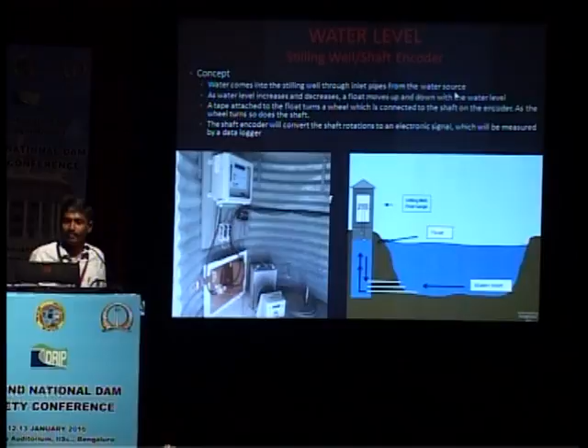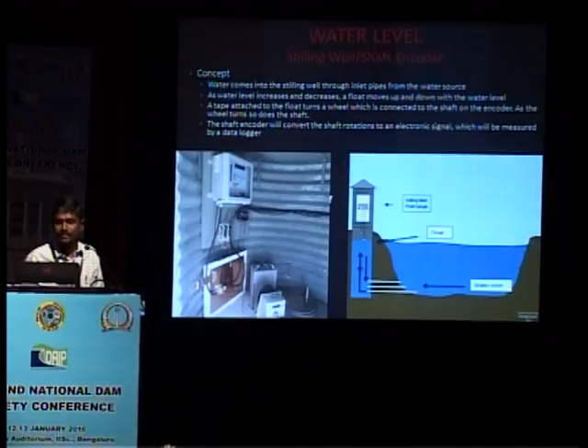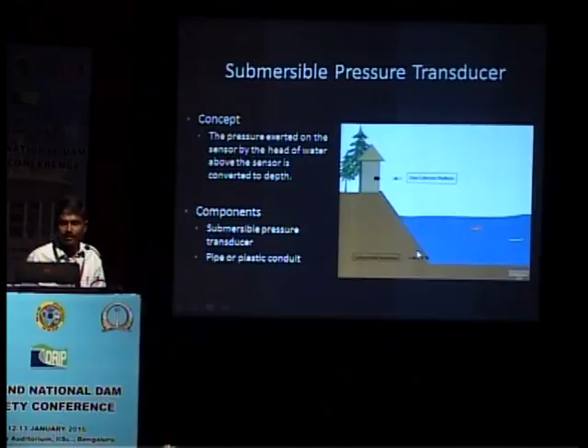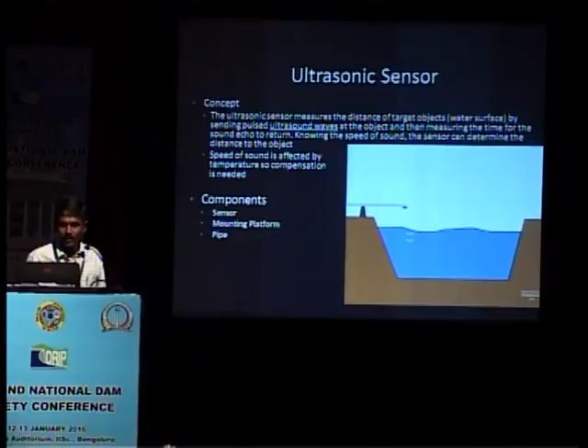In water level, you have various ways of measuring it. This is shaft encoder type, which is very traditional and comfortable to use. And submersible pressure type sensor, which is a replacement for the bubbler that is being practiced now. Because of the disadvantages encountered in bubbler, and ultrasound is very commonly used, but it has a problem - you have beam width restrictions. The beam should not touch any connections or the dam somewhere. So that has been overcome by radar technology.